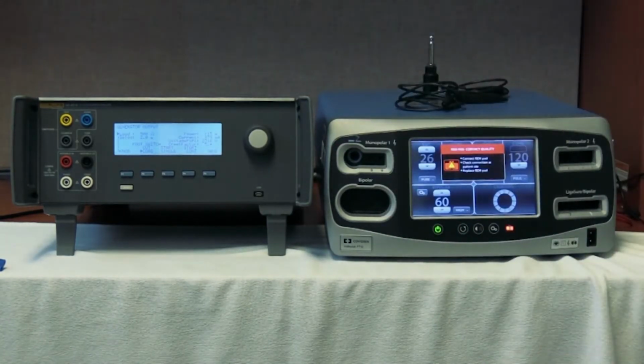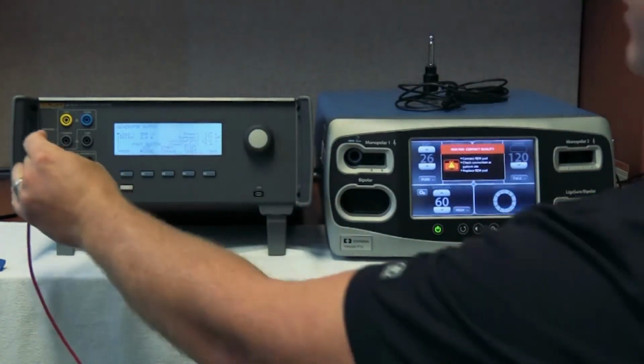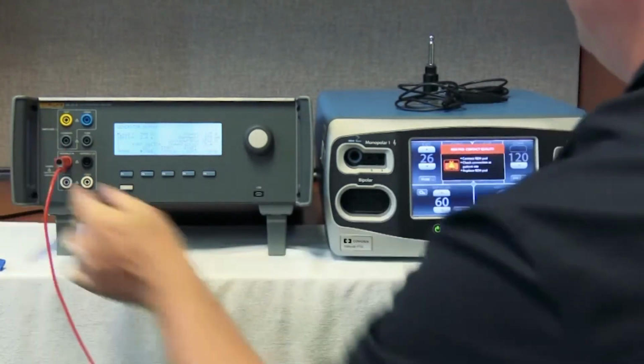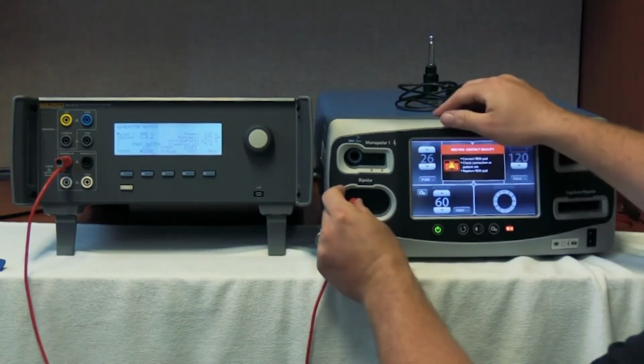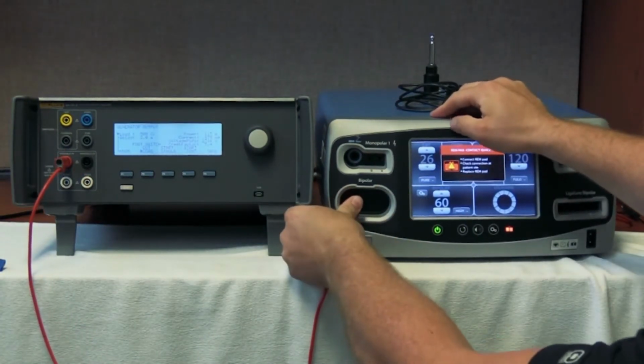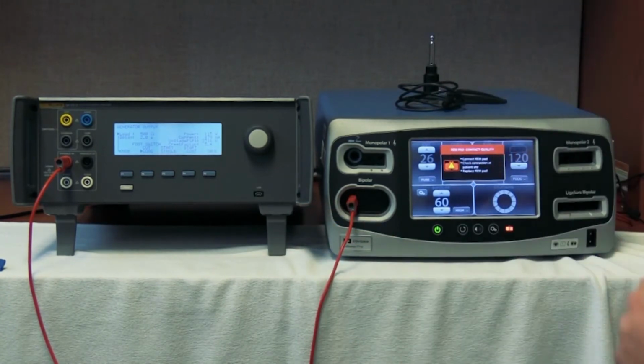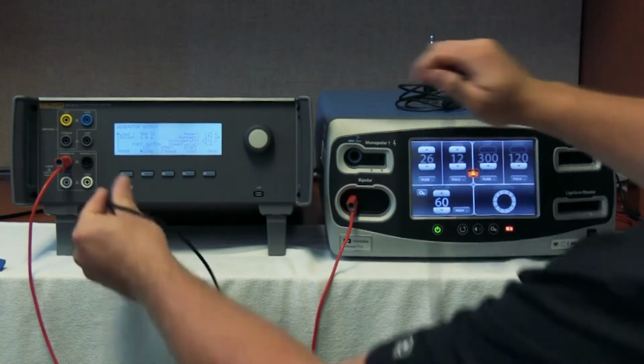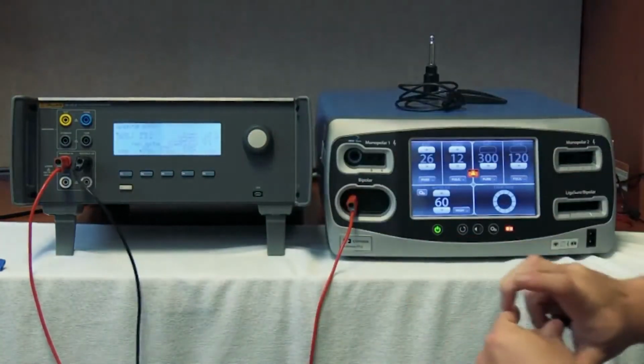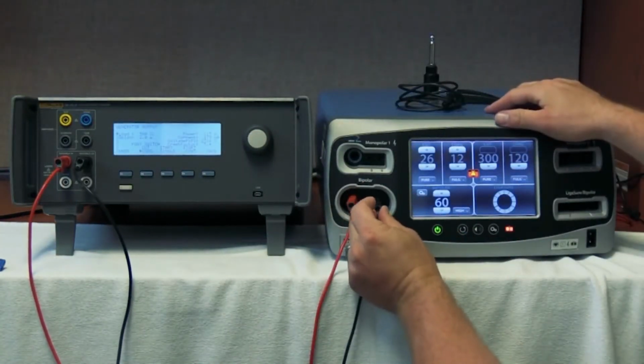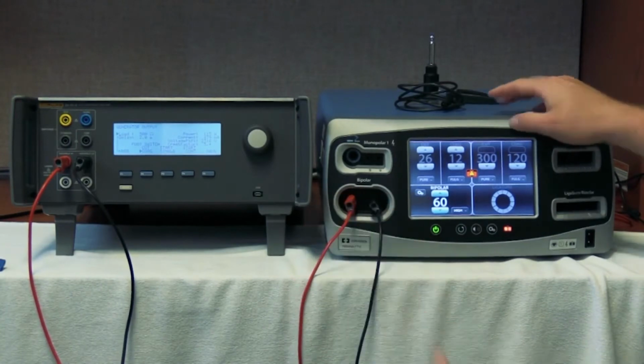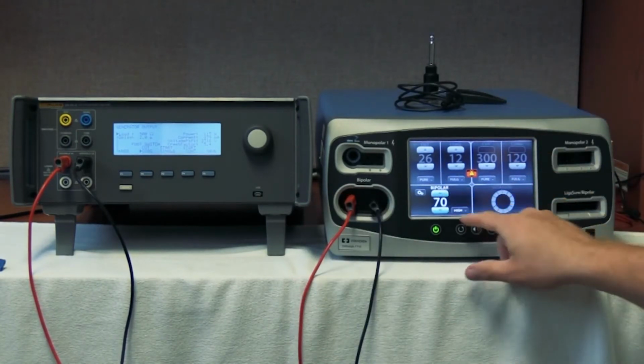For bipolar, we're going to use our red cable. We're going to go to the variable high and the left port of the bipolar, and we'll take our black cable and go from variable low to the right port. There we go, now our bipolar is activated, but we don't have the pedal here, so we can't activate this.